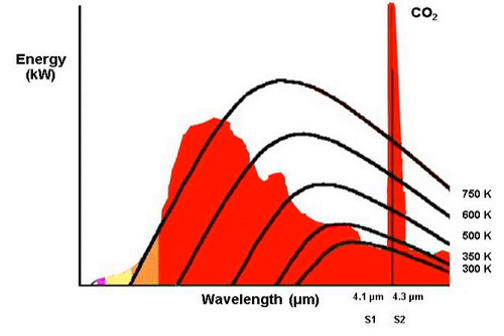At 700 K a hot object, a black body, starts to emit visible light glow. Dual or multi-infrared detectors suppress the effects of heat radiation by means of sensors which detect just off the CO2 peak, for example at 4.1 micrometers. Here it is necessary that there is a large difference in output between the applied sensors, for example sensor S1 and S2 in the picture.